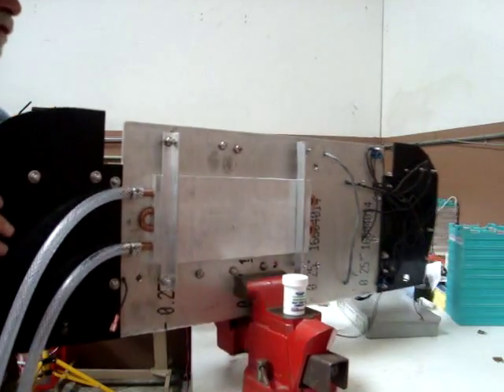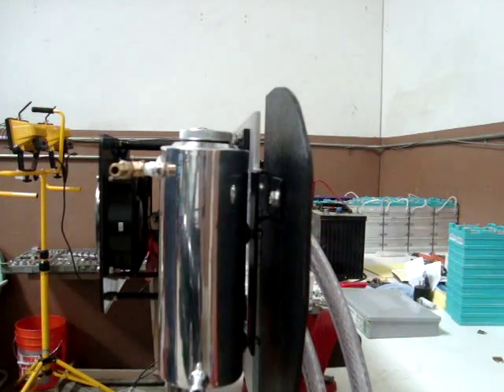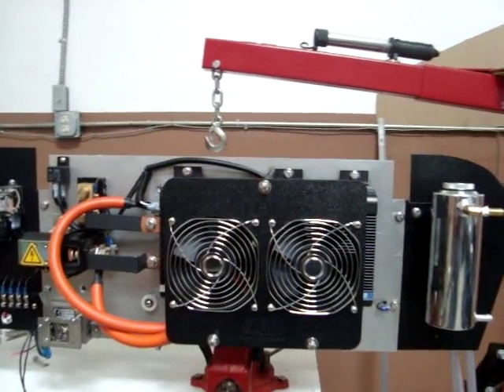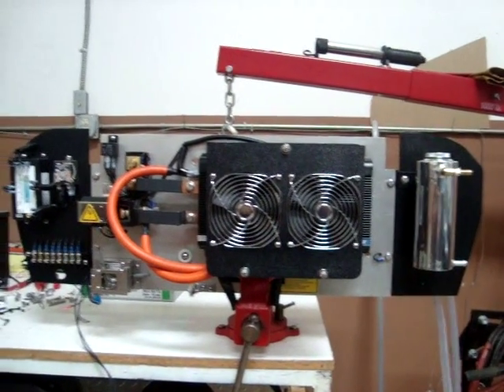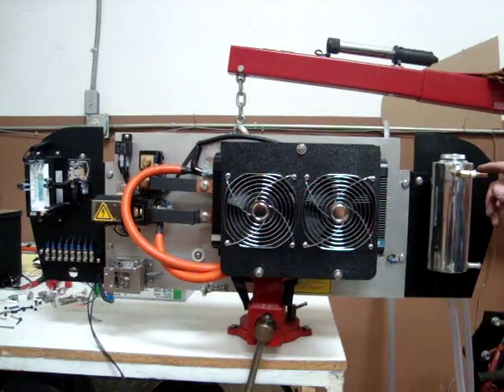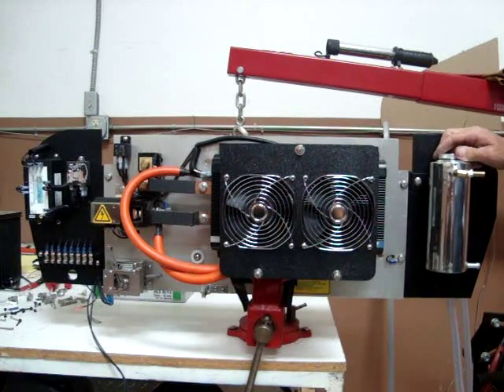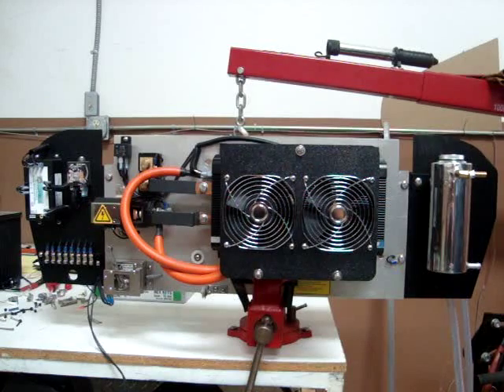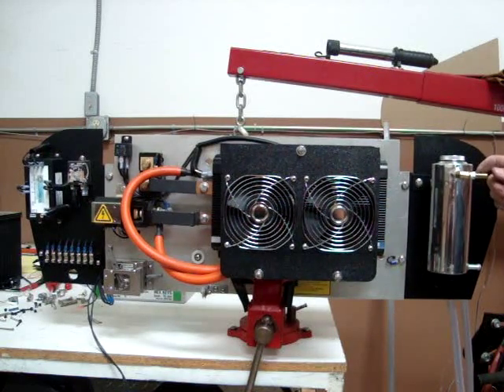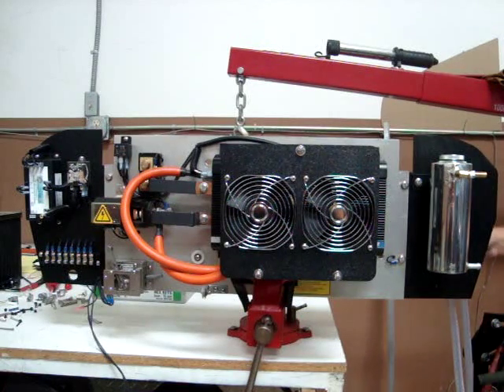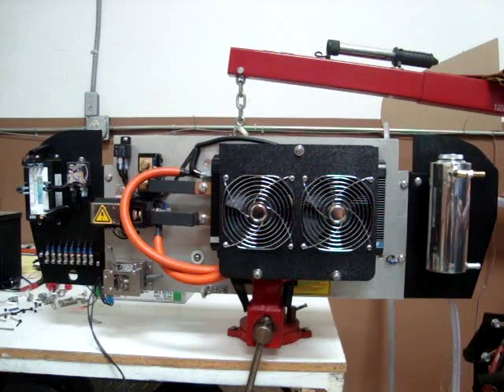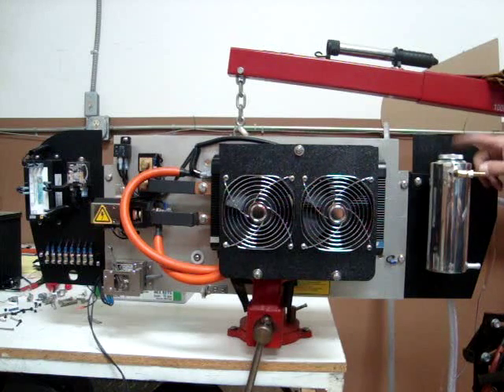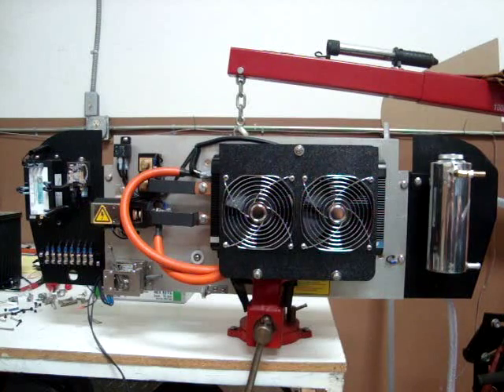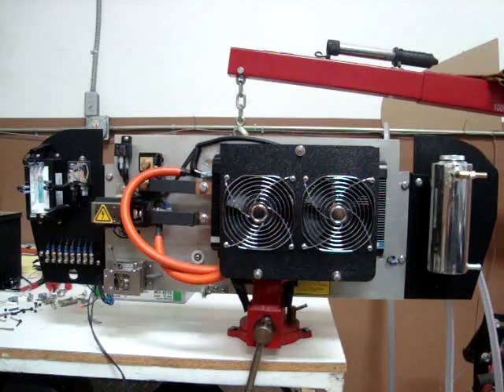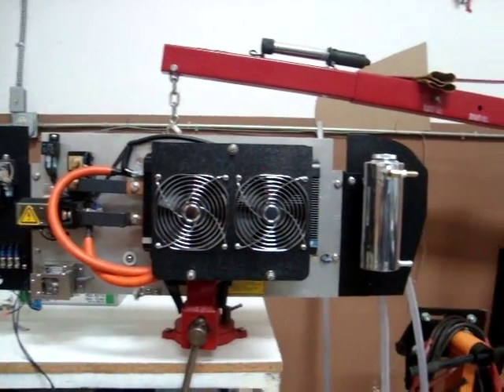Let me show you the front side here. This is the front side with our reservoir mounted. This is something we bought off the shelf, which was actually for a different application, so we had to add a fitting and route it where we want it to go. This happens to be, just as we desired, our highest point in the system, so the return on our reservoir will be at the highest point in the cooling system, which gives us good flow.